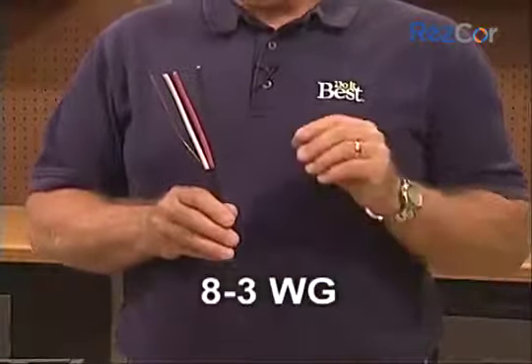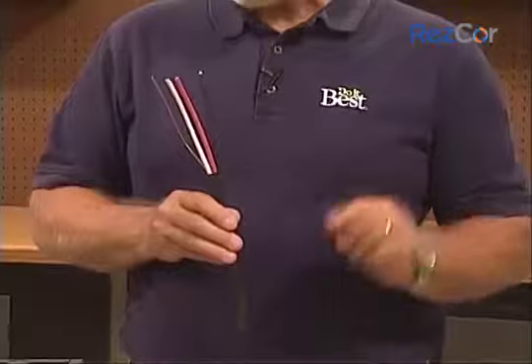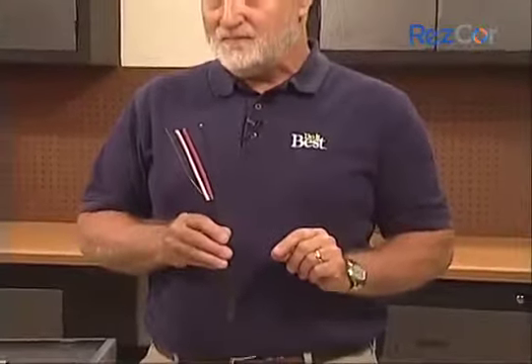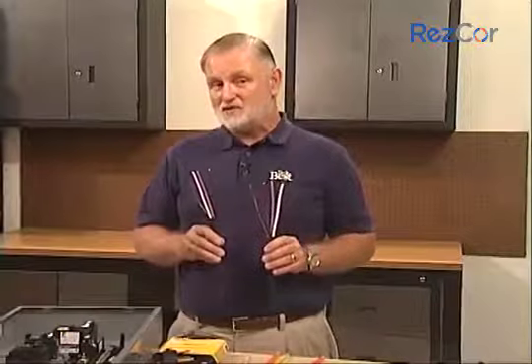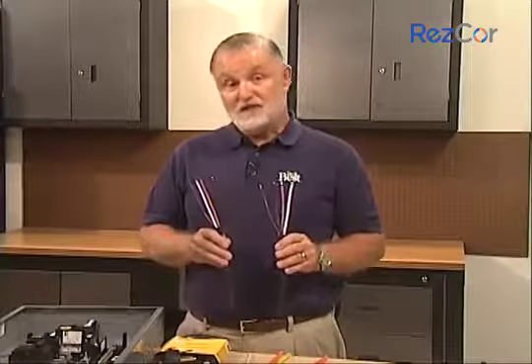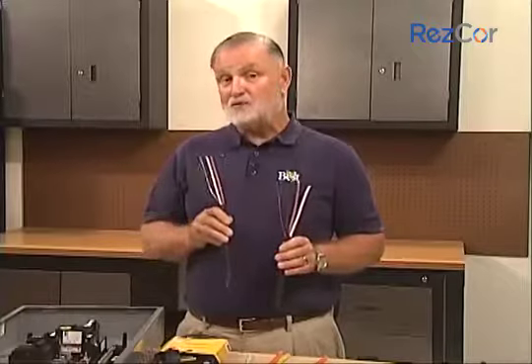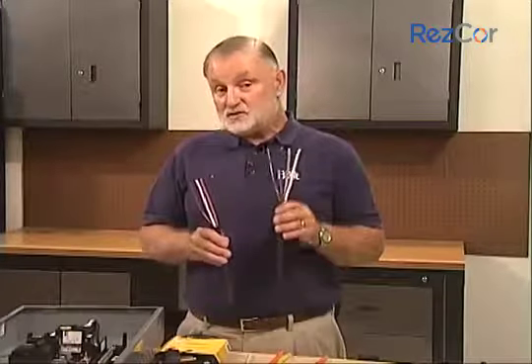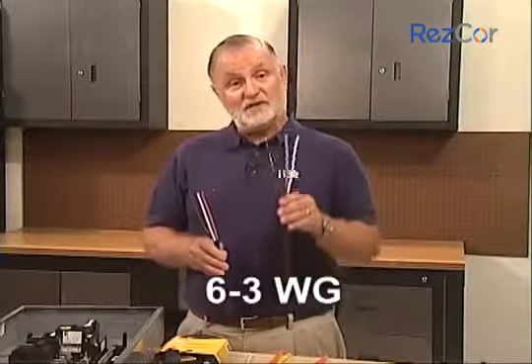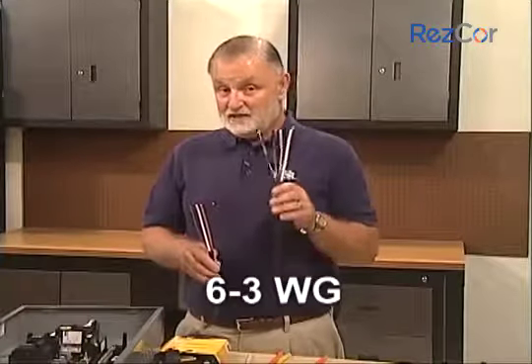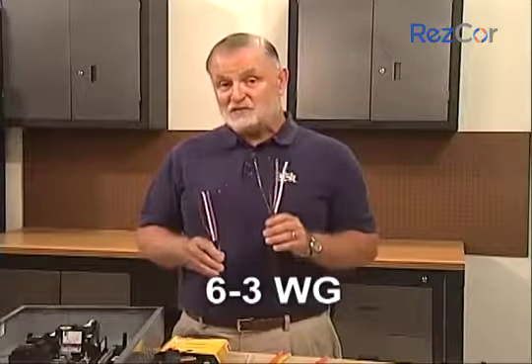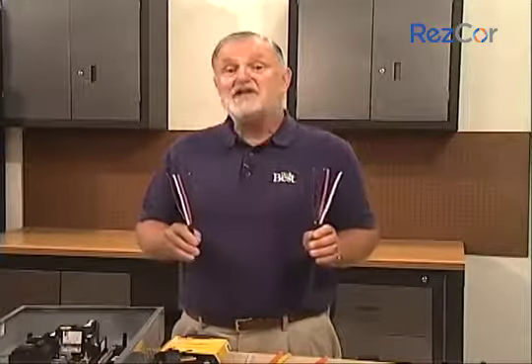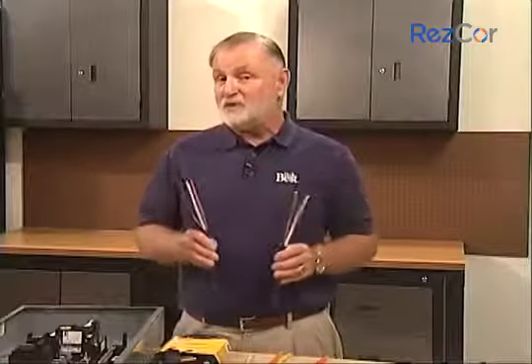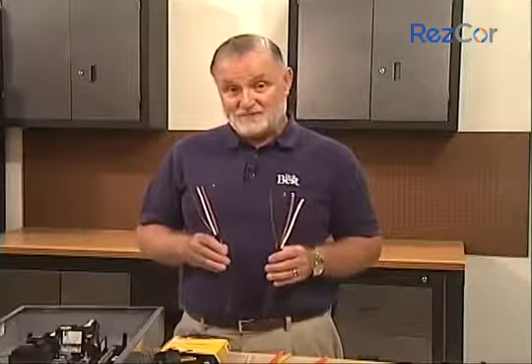When you help a customer select a cable, it's important to help them think about what they may do at some time down the road. Lots of people will upgrade their appliances over the years. A customer who currently has a regular electric range might someday purchase a range that has a self-cleaning feature. The problem is 8-3 cable won't be sufficient for the new range. To safely supply power to the new range, they'll need a bigger 6-3 cable. It's best to suggest the largest cable the customer might need in the future, because when the time comes that they need a larger cable, they probably won't change it, and that could lead to a fire.